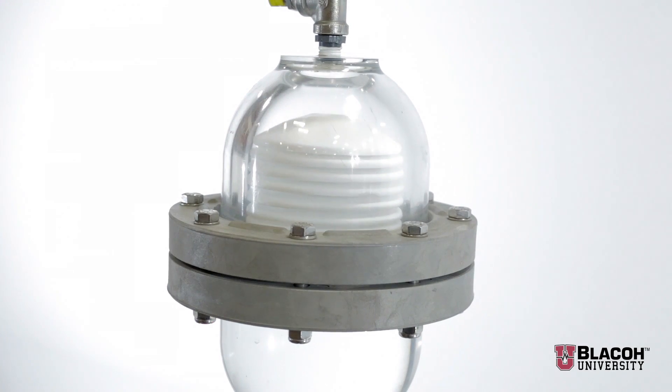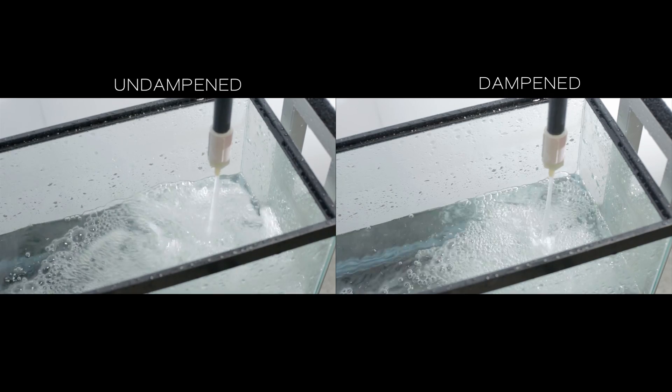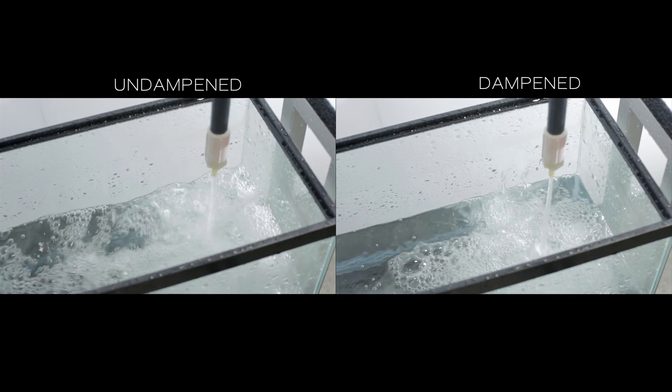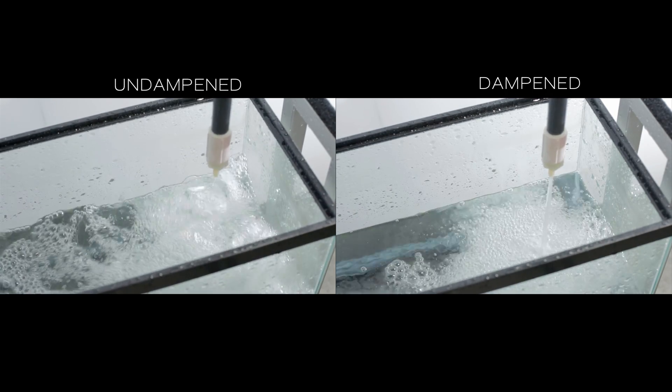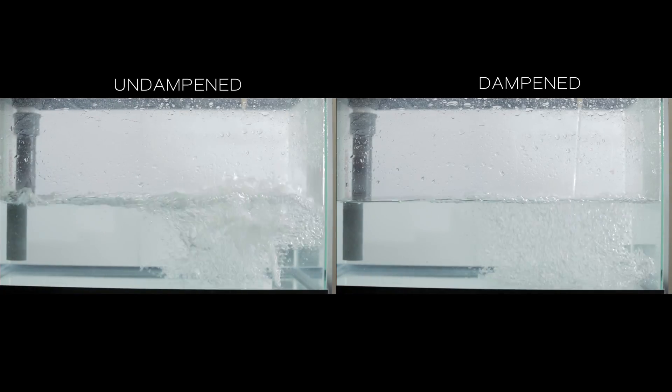As you can see with the benefit of the dampener, discharge fluid is kept in motion. Each stroke of the pump fills the dampener, and then the dampener discharges fluid when the pump is on its suction stroke, creating a smooth system.